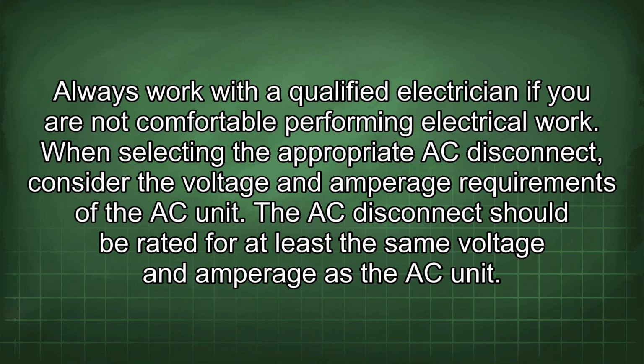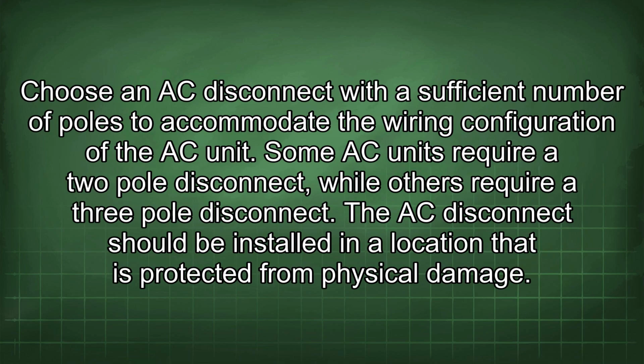When selecting the appropriate AC disconnect, consider the voltage and amperage requirements of the AC unit. The AC disconnect should be rated for at least the same voltage and amperage as the AC unit. Choose an AC disconnect with a sufficient number of poles to accommodate the wiring configuration of the AC unit. Some AC units require a 2-pole disconnect, while others require a 3-pole disconnect.